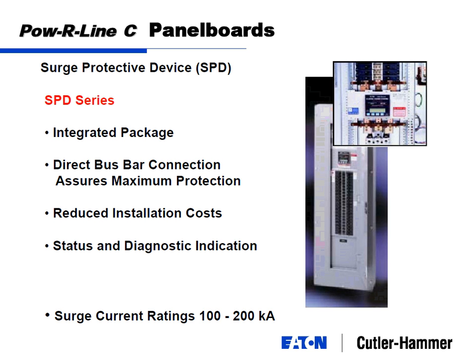Okay, the lightning surge, I'll call that the Mike Tyson. The one hit, you could be out. And if this thing absorbs the lightning strike, shunts it all to ground, and fails, it does its job. I mean, that's what it's there to do, to save everything else. The other transient overvoltage source is coming from the inside of the building. Now, from the inside of the building, they can be just as damaging as the transient coming from the outside of the building, just in a much different way.